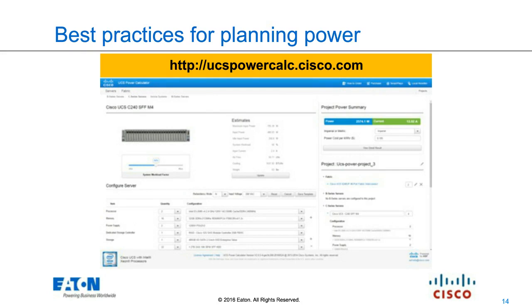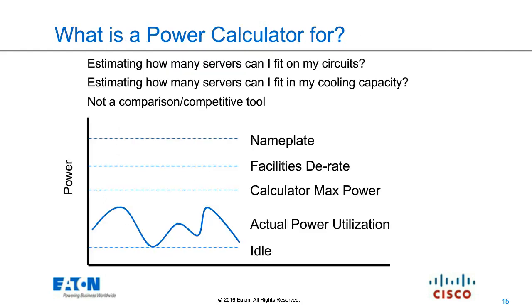The first thing for planning power is we'd always recommend going to the vendor's power calculator. In our case, the Cisco Power Calculator, which you can find at ucspowercalc.cisco.com. You configure the system and it gives you an estimate of how much power it will use. We always have to be careful about what a power calculator is actually used for - it's for estimating how many servers you can fit on a circuit. So if you have a 20 amp 110 or a 30 amp 208 circuit, how many servers can you put on that circuit without worrying about the breaker popping or getting to the 80% limit?